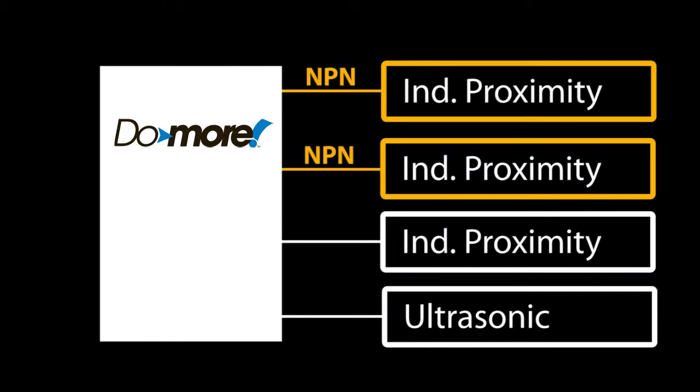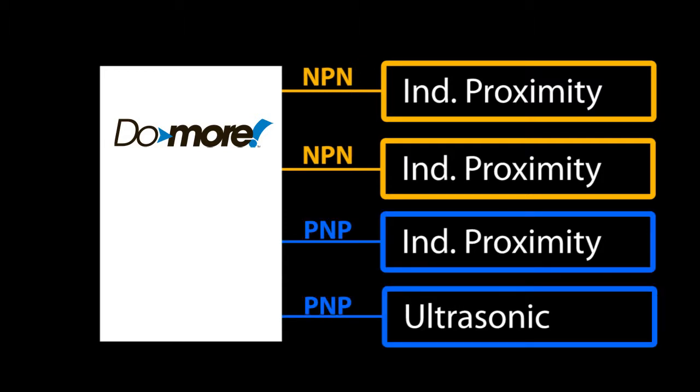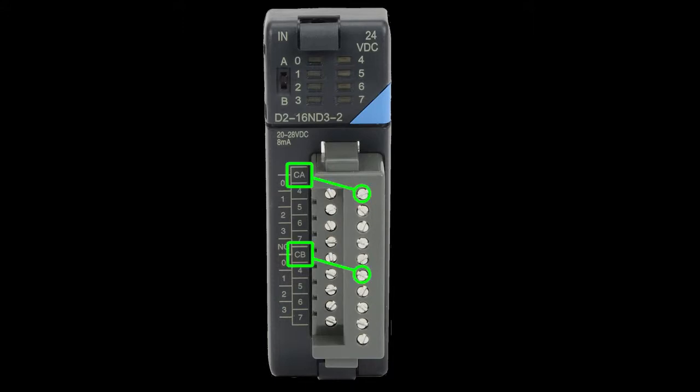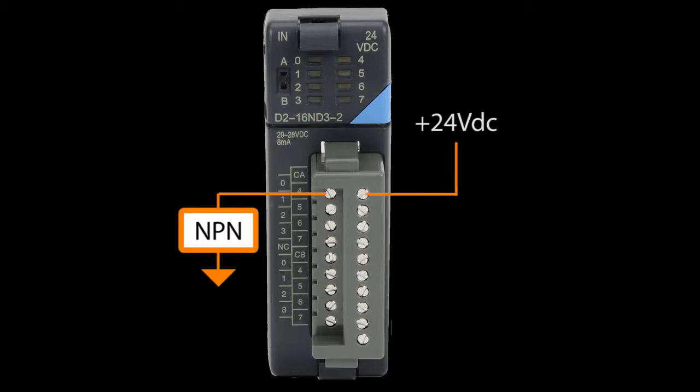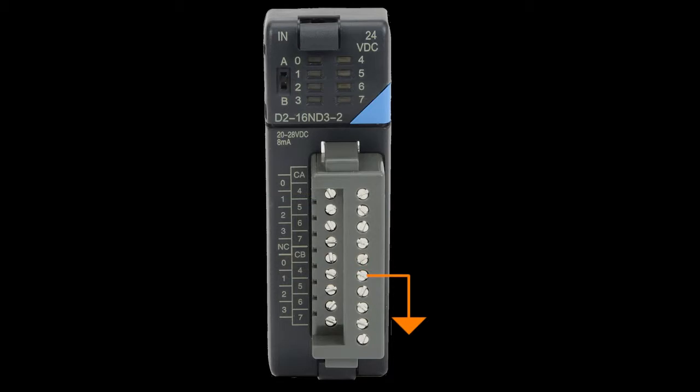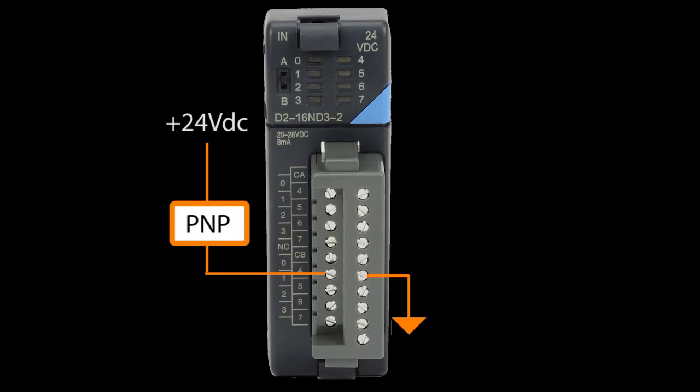Two of the proximity sensors are intentionally NPN and the other prox and ultrasonic are PNP – just so you can see how to connect the different sensor types to your controller. Since we have both types of sensors, we need to make sure the PLC input module can handle both NPN and PNP. This Do-more input module has two commons. That's perfect because we can simply connect one common to the positive voltage rail, so the NPN sensors can pull the IO terminal low when they activate. And we'll connect the other common to the negative rail, so the PNP sensors can pull the IO pins on the PLC up when they go active.